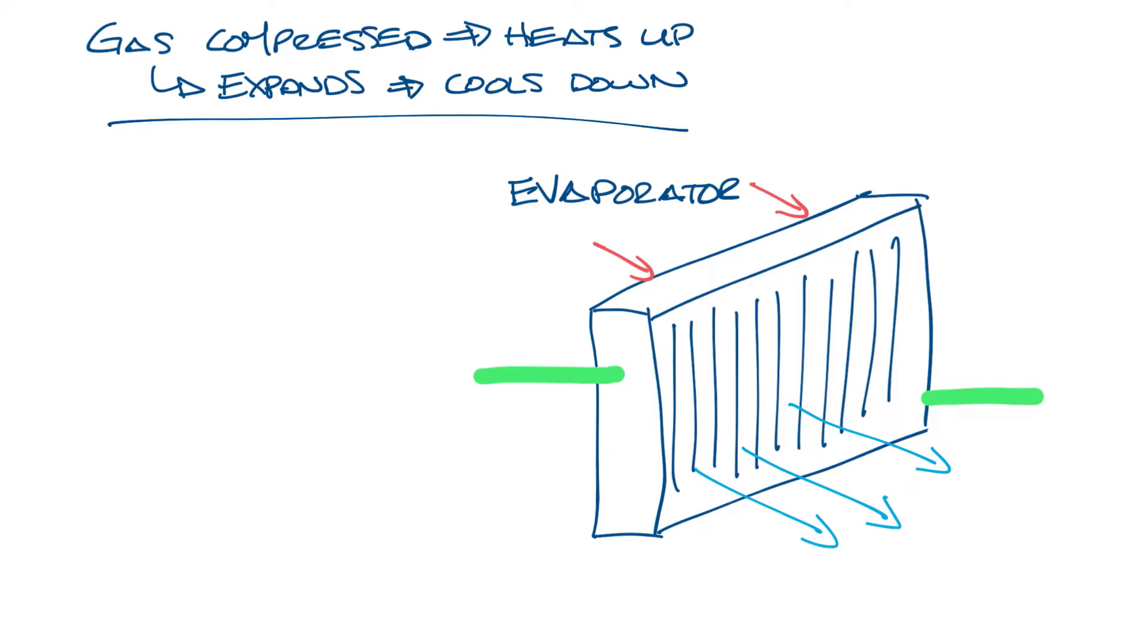The transfer of heat from the air to the refrigerant lowers the temperature of the air, so it can be delivered to the occupied space for cooling. It also causes the refrigerant to evaporate. So say you have 40 degree liquid refrigerant going into the evaporator. After the air passes through and the heat transfer happens, it comes out at, say, 50 degree vapor. So this is your evaporator.